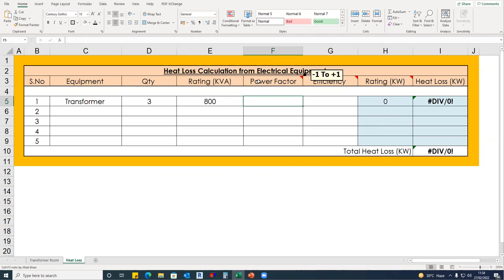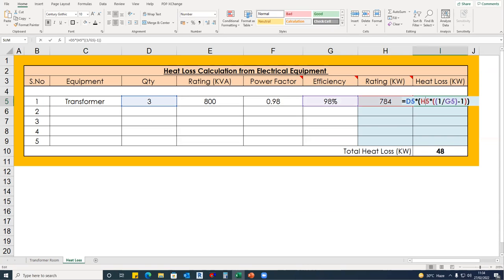Power factor. So power factor ranges from -1 to +1. Okay, you can ask the electrical consultant what it varies in your case. I'll take 0.98 in our case. Efficiency of the transformer varies from 95% to 99%. In this case, I'll take, for example, 98%. And based on the formula, you'll get the electrical kilowatts, 784. So this is the electrical kilowatt, but we need the heat dissipation. For heat dissipation, we have another formula that I have used over here. And you can check this formula in detail in the DG room ventilation video. I have explained this in detail. So total heat loss from these three transformers is 48 kilowatts.